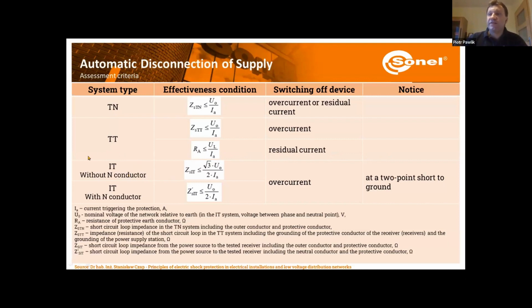And further on, in case of the IT network, here the transformer is insulated from the ground. So in case I would grab the phase conductor, nothing will happen. So here we need to consider a 2-point short to the ground, so that our fault loop could be closed. And here we can have different types of IT systems with or without a neutral conductor. And these are the equations describing the effectiveness condition.